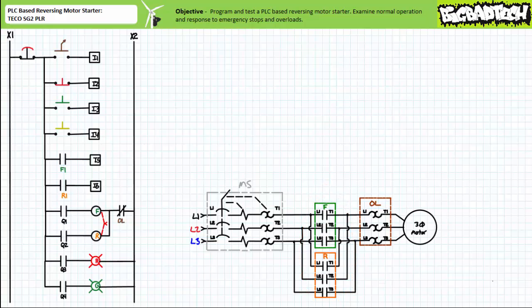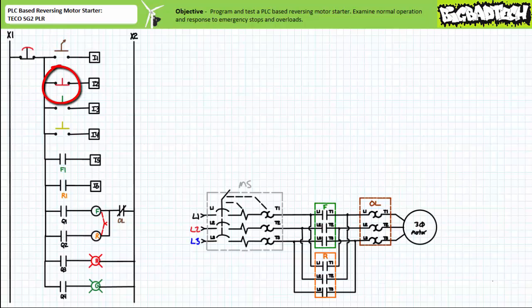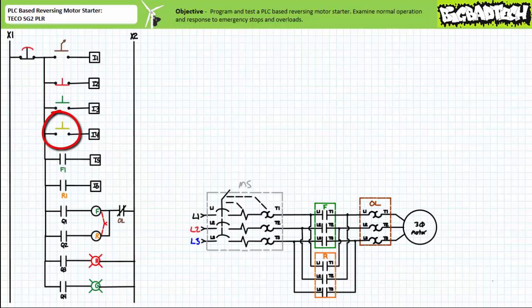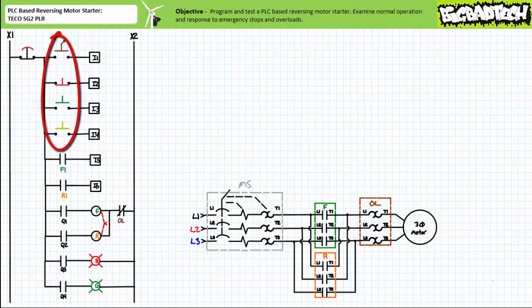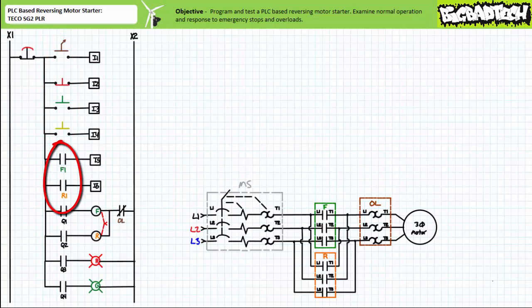The PLC has been configured with the following field input and output devices: a normally open maintain contact selector switch on input 1, a normally closed momentary contact red push button at input 2, a normally open momentary contact green push button at input 3, a normally open momentary contact yellow push button at input 4, the normally open auxiliary F1 contact of the F contactor on input 5, and the normally open R1 auxiliary contact of the R contactor on input 6. The first four field input devices are intended for human-initiated interaction, whereas the auxiliary contacts on inputs 5 and 6 serve as feedback about the status of a particular contactor.